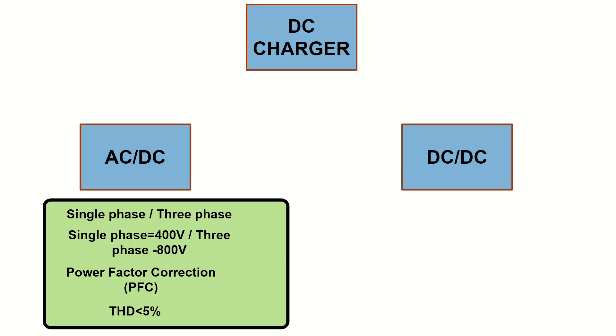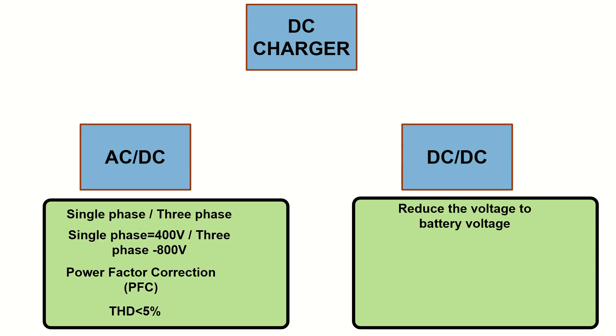The DC-DC stage is the second level of power conversion. It converts the stable DC link voltage into a lower DC voltage to charge the battery. The DC-DC converter must be capable of delivering rated power to the battery over a wide voltage range, and also charging the battery at constant current and at constant voltage mode, depending on the state of charge of the battery. The DC-DC stage also provides galvanic isolation between the input and output through high-frequency transformer. These converters are capable of operating at zero-voltage switching and zero-current switching, achieving very high efficiency.